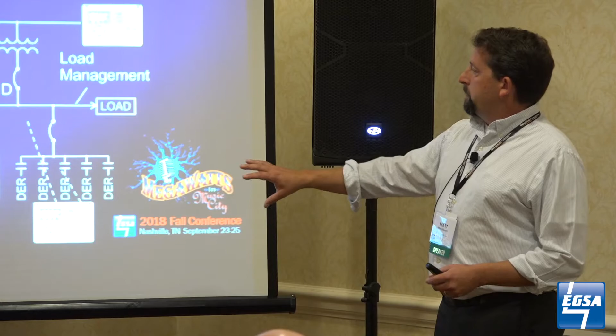They also wanted the ability to take their utility grid and tie it back into the utility for peak shaving. So all the data from each of those resources, the distributed energy resources, the buses—they wanted to monitor all these loads. All of that has to be monitored: breaker statuses and synchronization across any of those utility ties are all tied together, and that data is communicated between each individual control system and control scheme, then fed back into a main hub or SCADA system, which can be remotely monitored. So all of this data can be tied remotely.